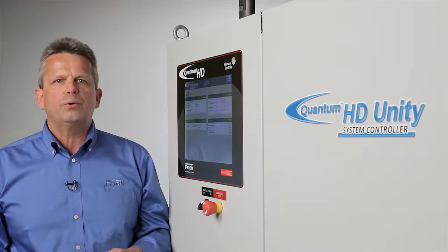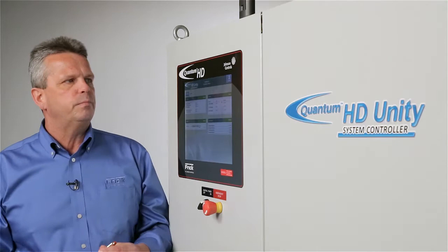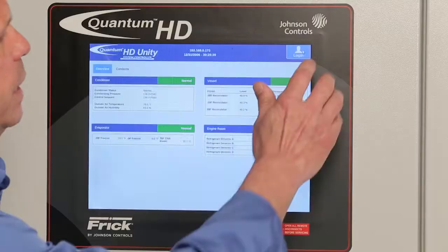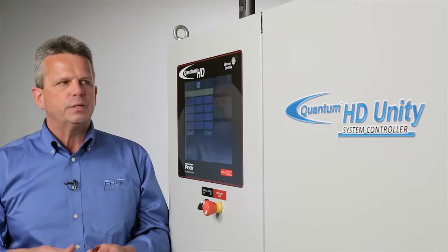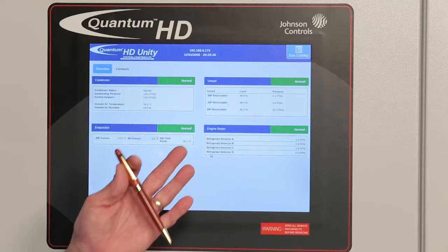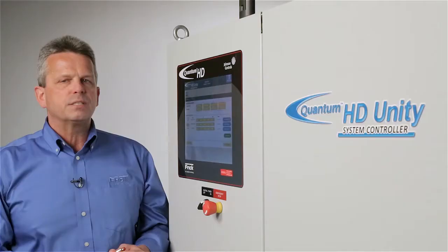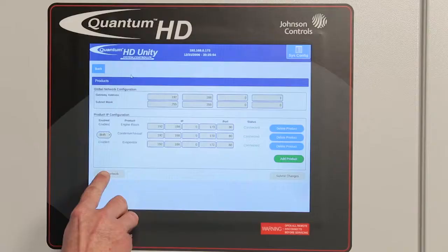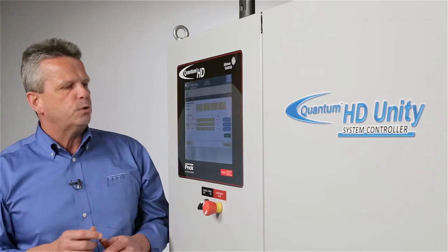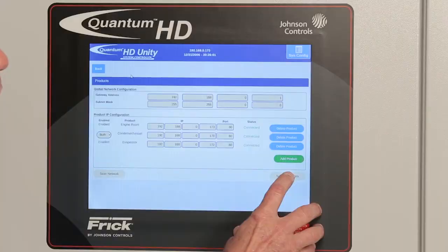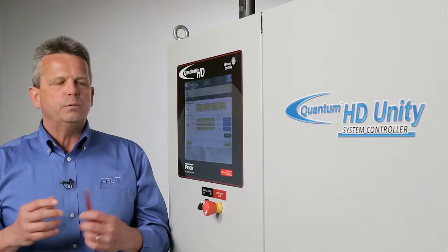Now we want to show the system configuration, which is the first step to the total configuration of all the individual parts and components of the Quantum HD Unity system controller. First, we need to log in by entering a login number that's been set up in the configuration. Once logged in, if you go into system configuration, you want to set up your network by going into system networking. Our network is already established, but if it were not, you would go in and do a scan network. Once done, you would hit submit changes to establish the components you'll be working with in this control system.